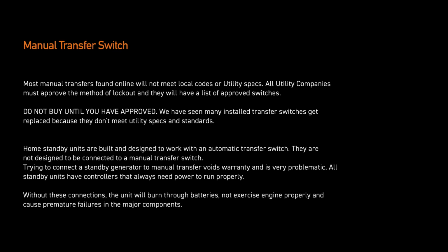Home standby units are built and designed to work with an automatic transfer switch. They are not designed to be connected to a manual transfer switch. Trying to connect a standby generator to manual transfer voids warranty and is very problematic.